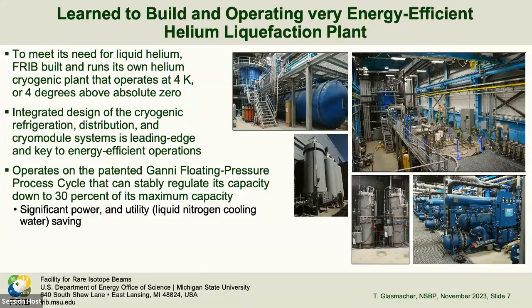The nice thing is when the load of the accelerator goes down, because you run less field, the helium use goes down. We recover the helium, but the heat load goes down, so we use less power to liquefy it. That saved us about 30% of the energy.